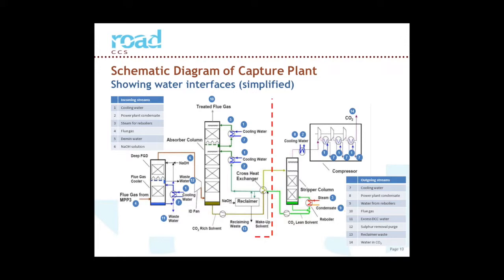Then we've got what Fluor call the overhead stripper condenser, or the stripper overhead condenser. So the CO2 comes out of the top of the stripper at around 100 degrees, and it needs to be cooled before going into the compressor, and cooling it also condenses a lot of the steam out that's come away with the stripper. And this is an area where we've managed to do some direct heat integration with the power plant. So this component is actually cooled by power plant condensate, so it provides feed heating duty to the power station.